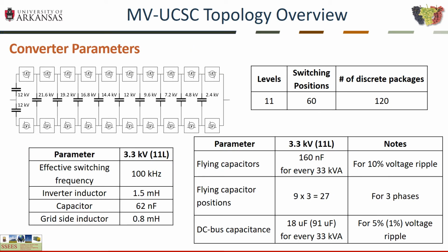This slide presents a summary of the topology. On the top left is the 11-level flying capacitor converter. Each switching position is 2.4 kV. The DC bus on the left is plus minus 12 kV. Then you have 9 flying capacitors, and those are the voltages they are subjected to. We have 60 switching positions, and we will explain in the next slide why we have 120 discrete packages. The effective switching frequency for this type of converter is the number of levels minus 1 times the switching frequency of a switching position. So 11 minus 1 is 10. The switching frequency of a switching position is 10 kHz, so what we have is 100 kHz.